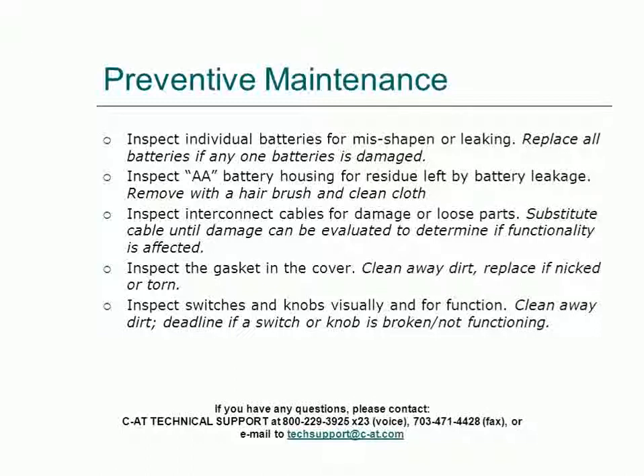Inspection of all the cables connected for damage or anything that might affect their functionality should be done prior to any deployment of the ICRI. In order to maintain the ICRI's waterproof operation, the gasket in the cover of the case should be inspected and dirt removed from it. If it is nicked or torn, that gasket should be replaced prior to deployment. Inspection of the externals and internal switches and knobs should be visual, and again, removal of dirt is the most important preventive maintenance, deadlining the unit if a switch or knob is broken or not functioning.